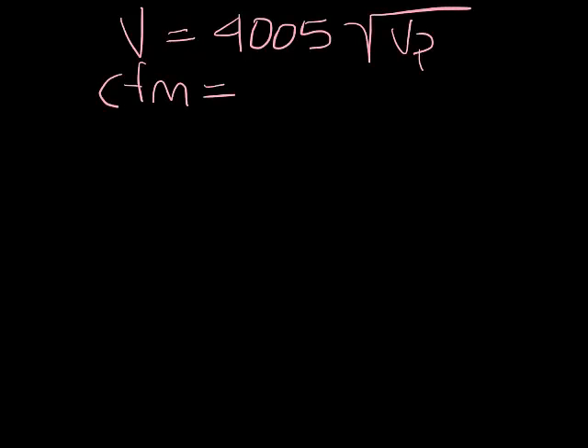Now knowing the velocity and area of the ductwork, we can calculate air flow, which is CFM equals the area times the velocity.